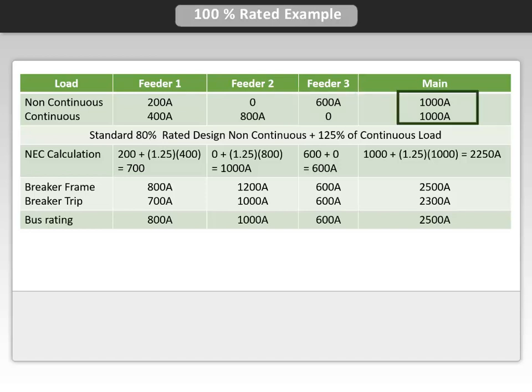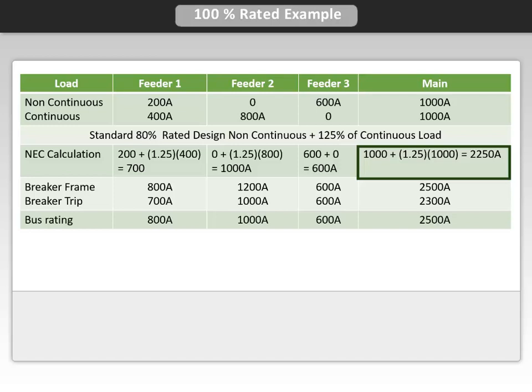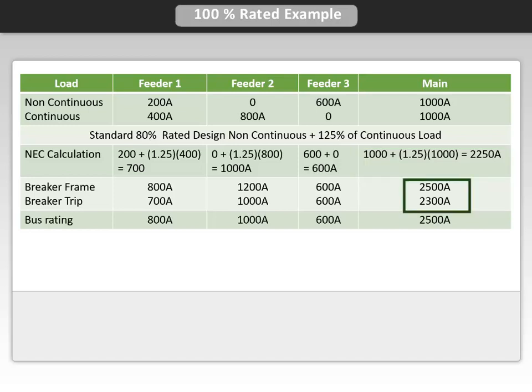When you total up the load, we have a 1,000 amp non-continuous and a 1,000 amp continuous. We take the non-continuous of 1,000 plus the derated value of 1,000 times 1.25 and determine that the required protection is 2,250 amps. The nearest size would require a 2,500 amp frame with a 2,300 amp trip.